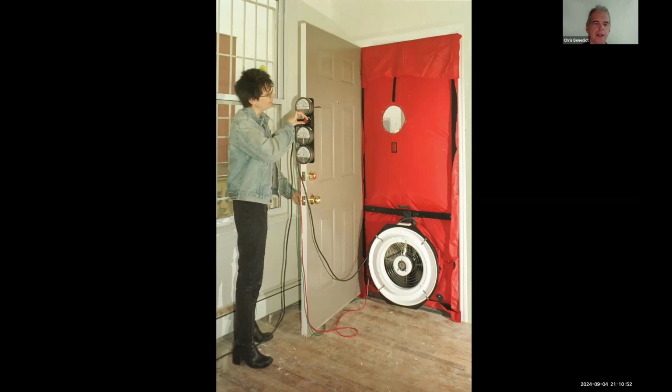So there are gauges there which measure the pressure difference between indoors and out. And there's a pitot tube, which measures air velocity. That's the way airplanes measure their speed. There's a little tube sticking out. I'll have a picture later in the presentation. So a pitot tube measures the velocity of the air, and the area there is known. Not that the air is flowing through all parts of that opening at the same speed.